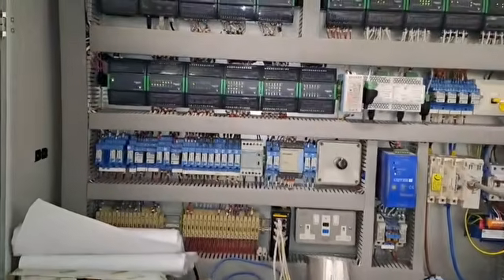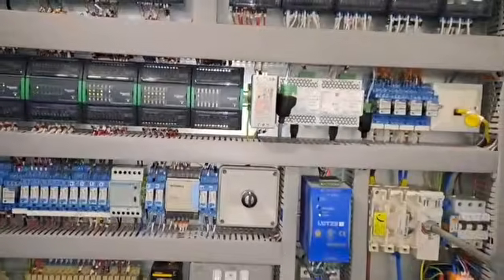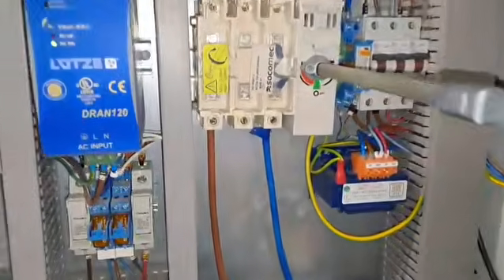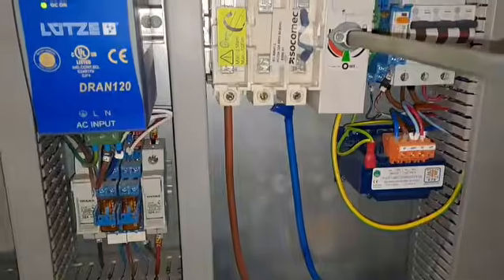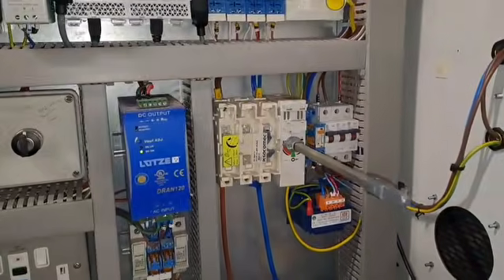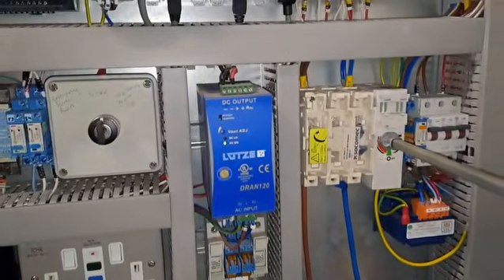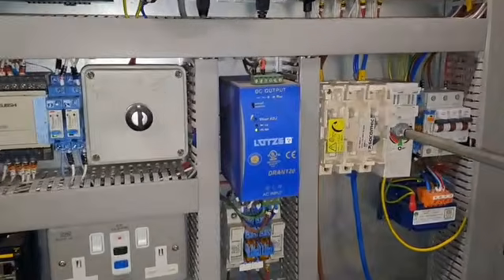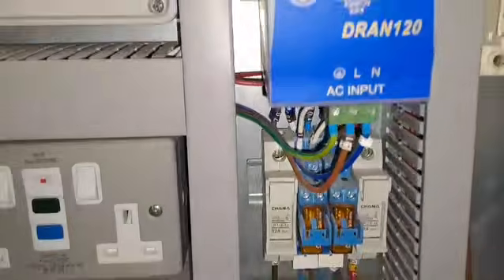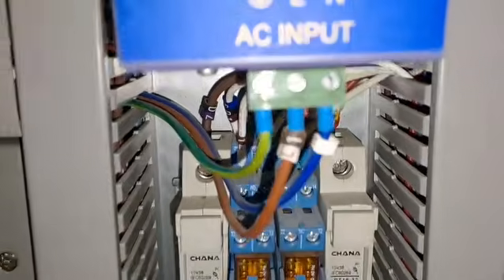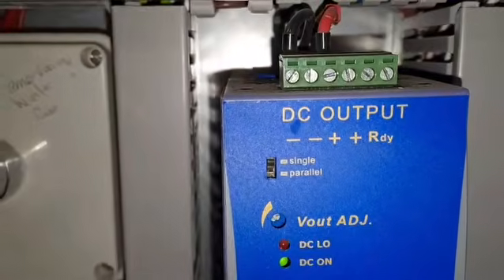I'm doing a little tour of a plant room, and this is the BMS first. We're starting off, and we have a live supply there and a neutral supply, so it appears to be single phase. Then they've got a lot of what looks to me like transformers. So here we have single phase coming in, and then you can see it converts to 24 volts DC.